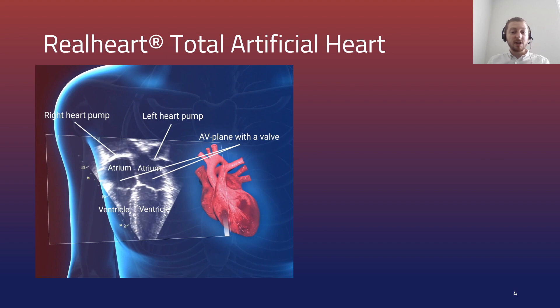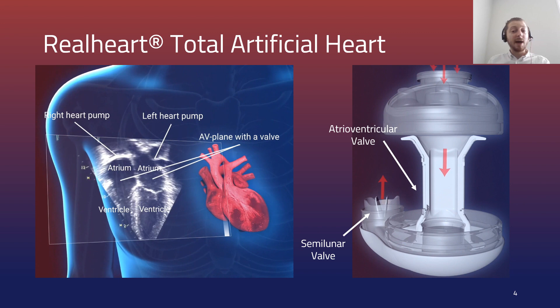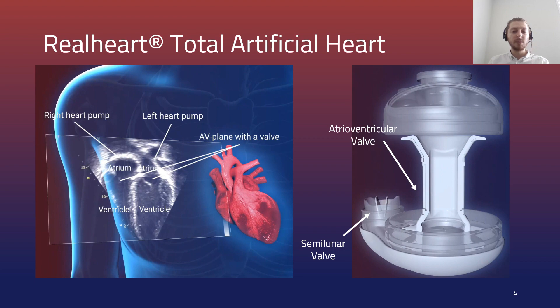It achieves this pulsatile flow by mimicking the mechanics of the native heart. The atrioventricular plane of the native heart can be seen to translate up and down to squeeze blood out of the heart. The Real Heart Total Artificial Heart uses this same technique coupled with a pair of bileaflet mechanical heart valves to govern the forward motion of the blood.